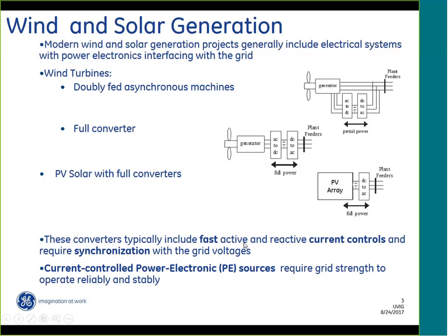In order to control current, particularly active and reactive current, you need a notion of where the grid voltage is. So you synchronize with respect to that voltage and inject an active or reactive current. All these concepts include some type of synchronization to the grid voltage. In general, current-controlled power electronic sources require some level of grid strength to operate stably.